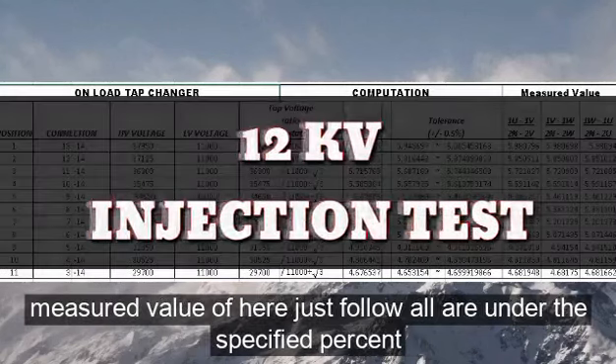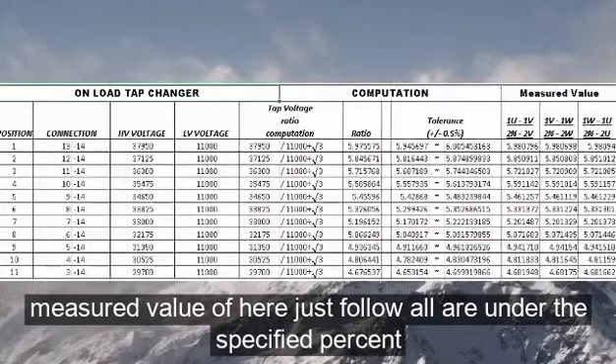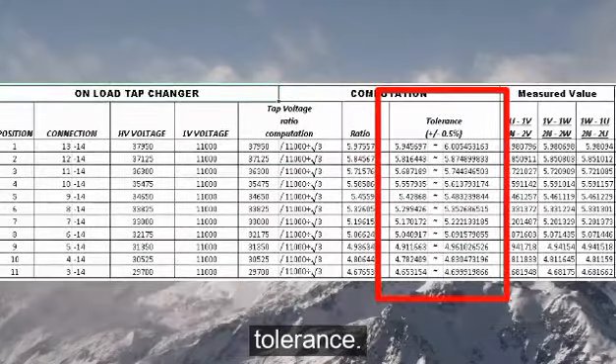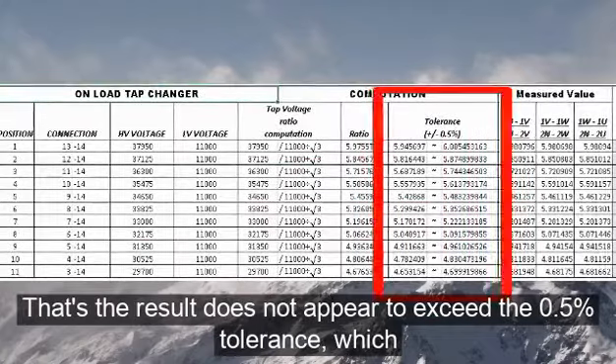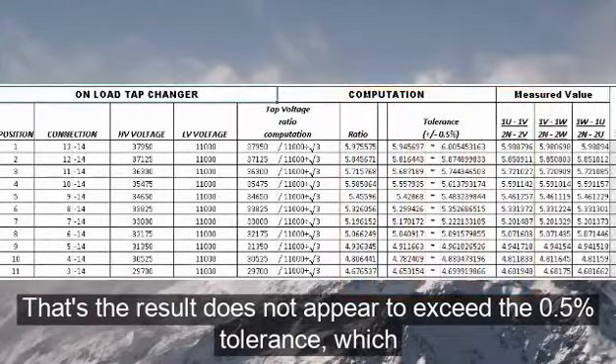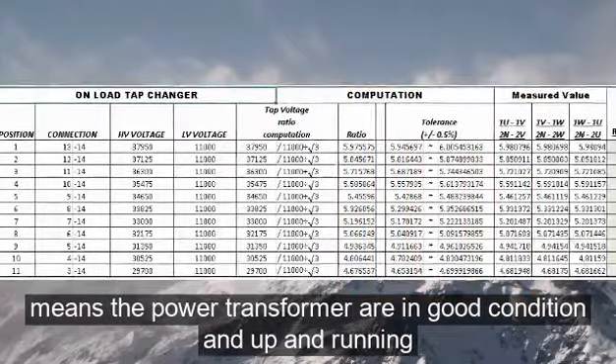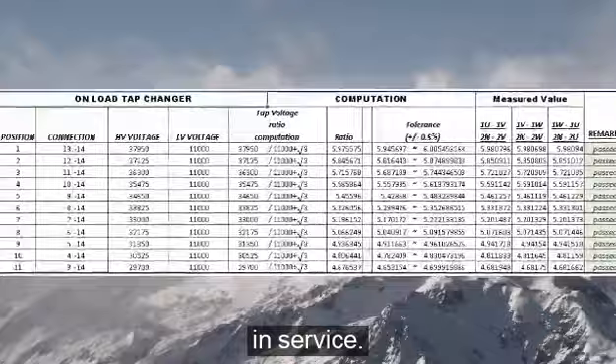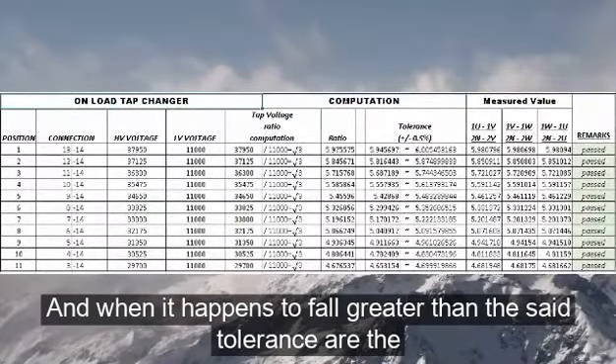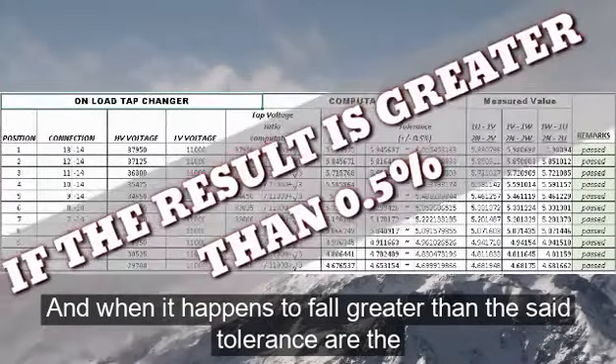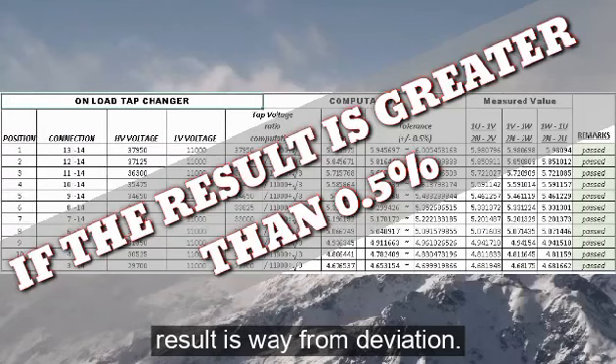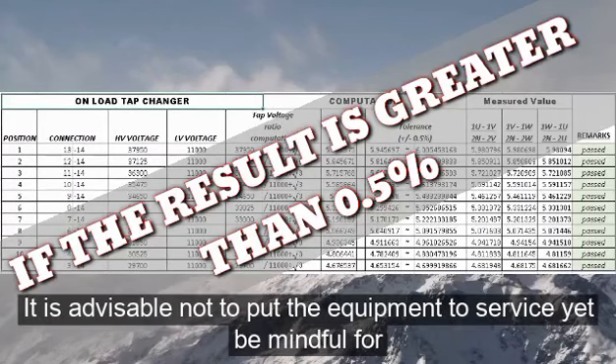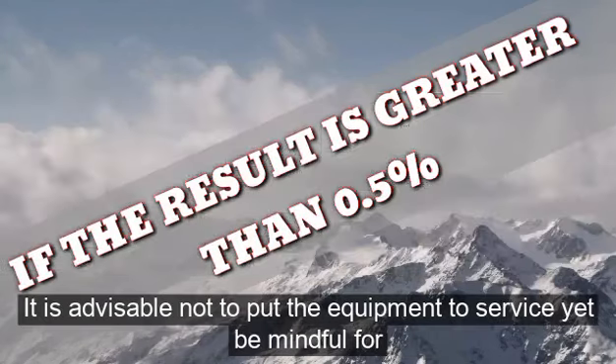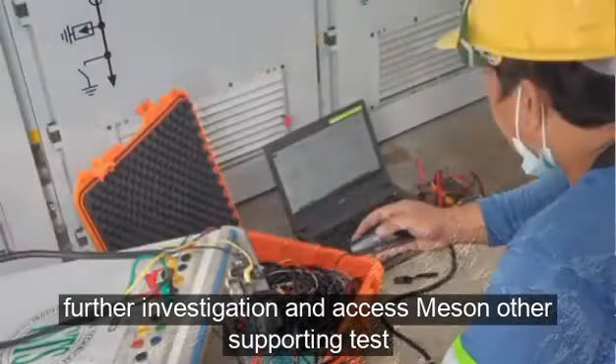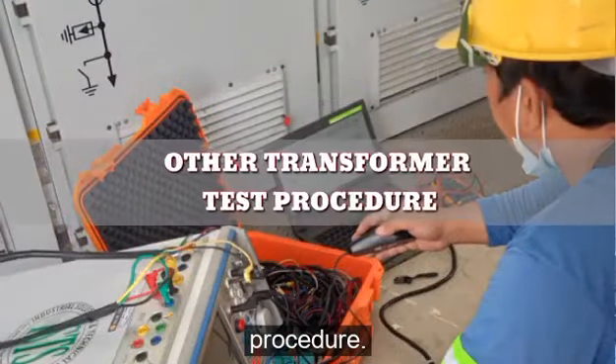In our test, the measured values appeared as follows. All are under the specified percent tolerance. Thus, the result does not exceed the 0.5% tolerance, which means the power transformer is in good condition and up and running in service. And when the result falls greater than the said tolerance or deviates widely, it is advisable not to put the equipment into service. Yet be mindful of further investigation and assessment with other supporting test procedures.